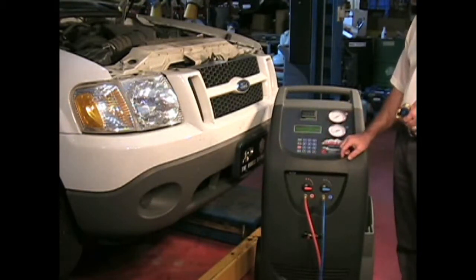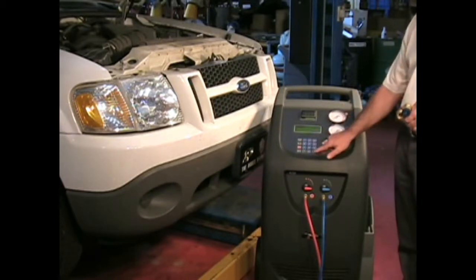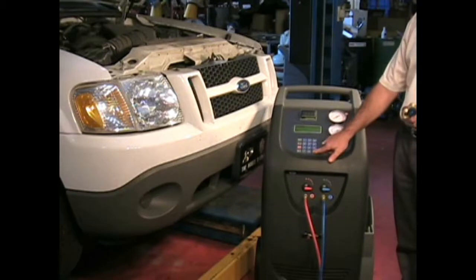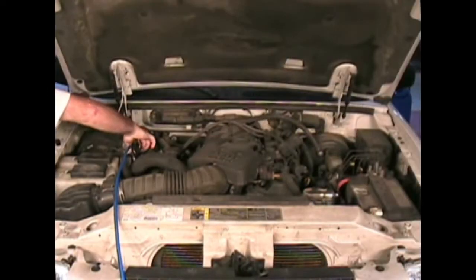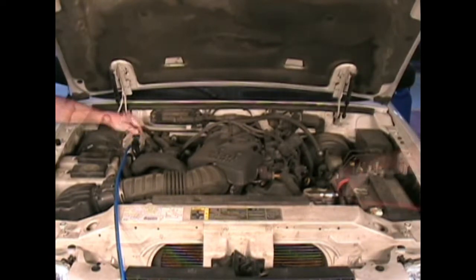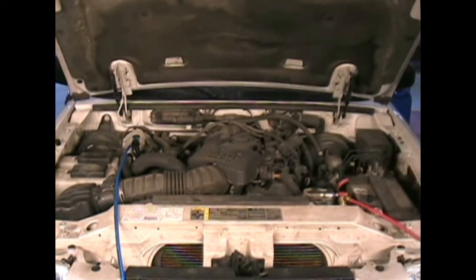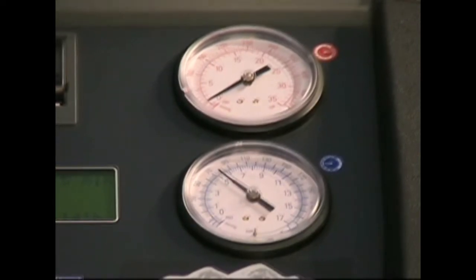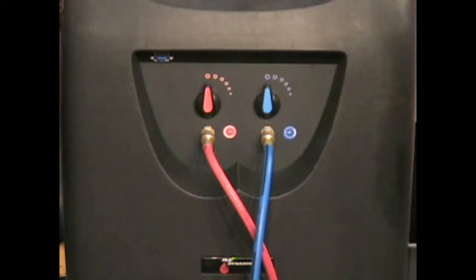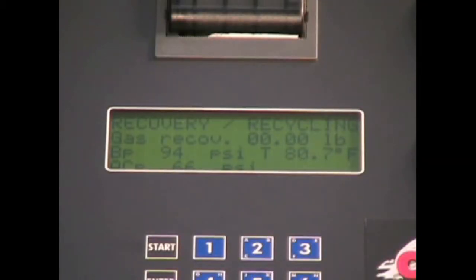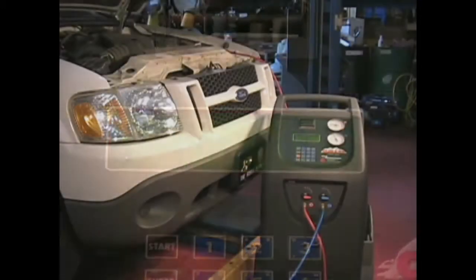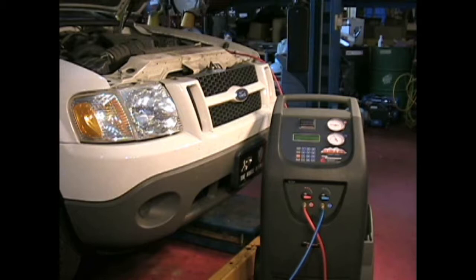To select a vehicle from the database, arrow to Refilling, and then press the down arrow key. Scroll to the vehicle being serviced and press Enter. The machine will retrieve and enter the refilling amount automatically. Connect service hoses to the vehicle and open the high and low side couplings. Observe the pressure gauges. Both will show system pressure if refrigerant is present. Open the high and low side machine taps and press Start. The machine will recover and recycle and purge oil and air if necessary. Then it will vacuum, leak test, add oil, and recharge the system.